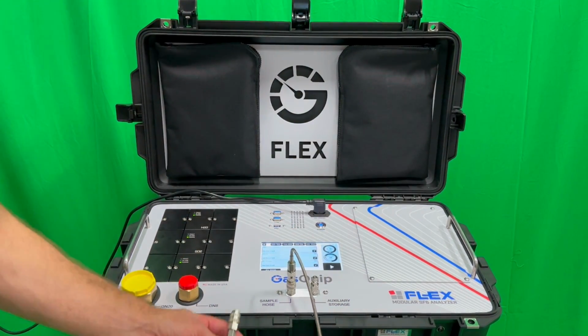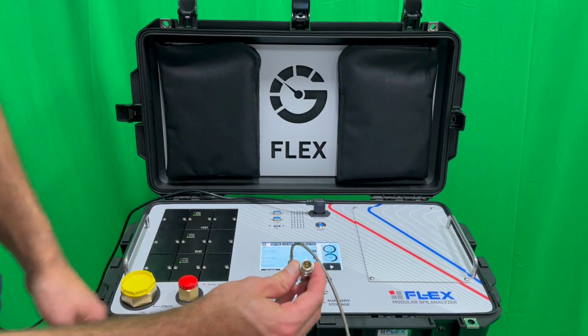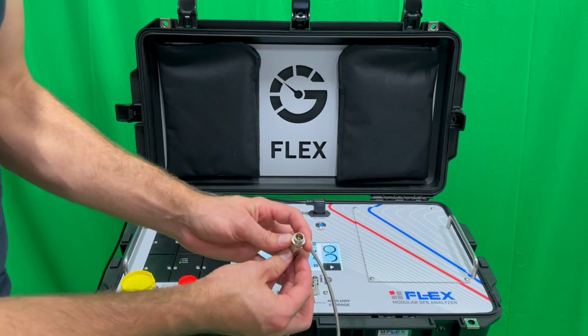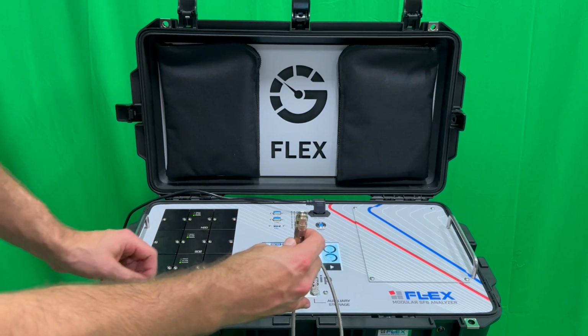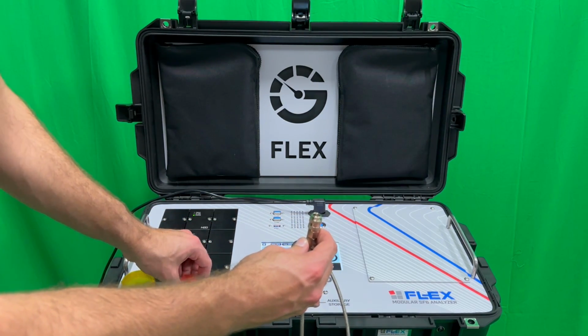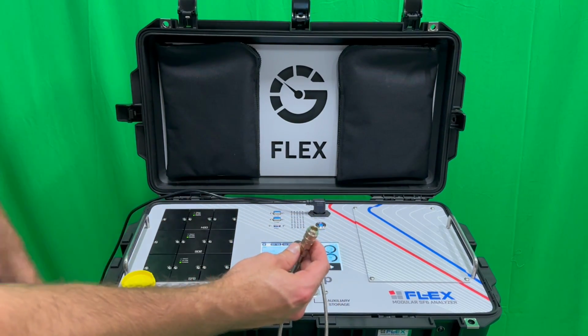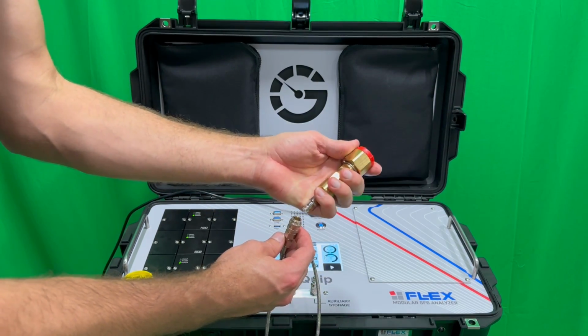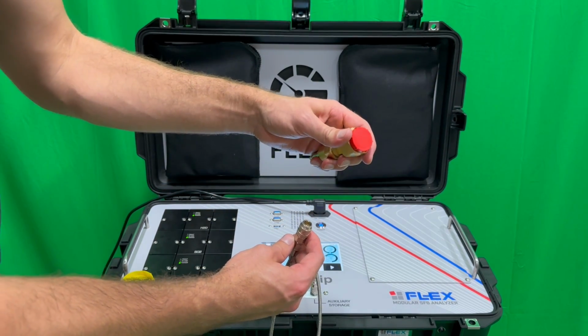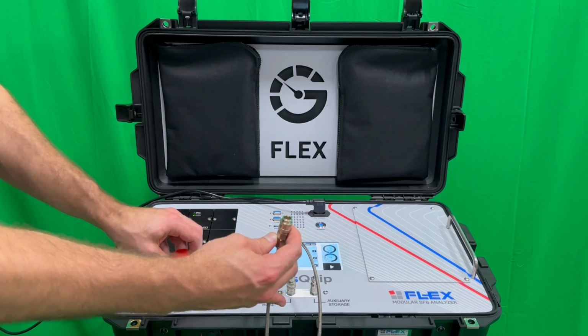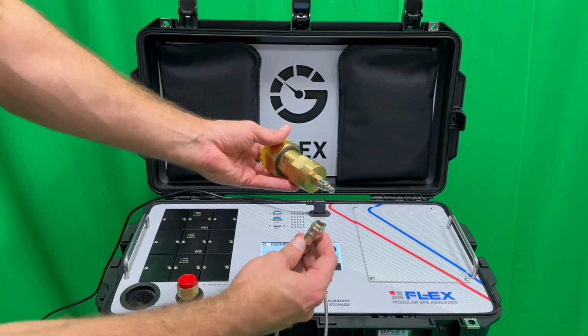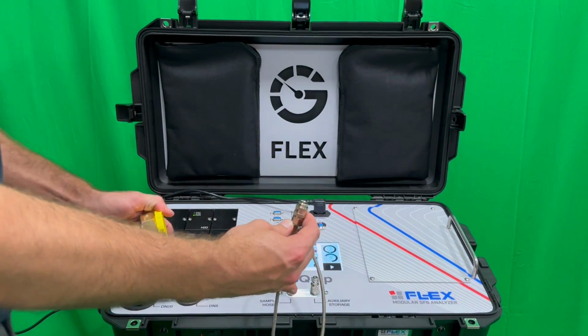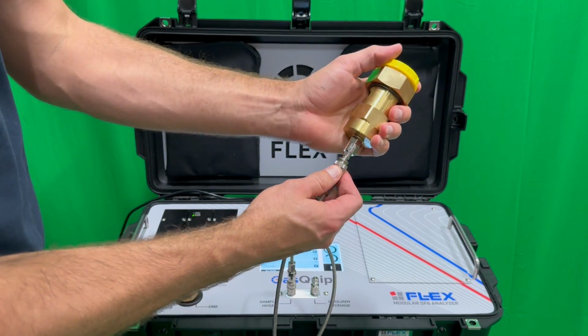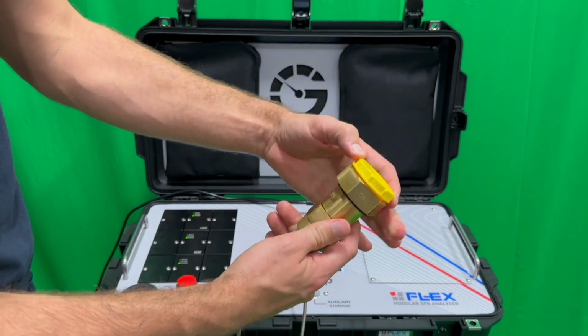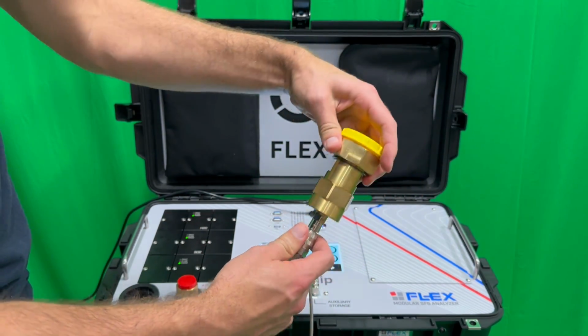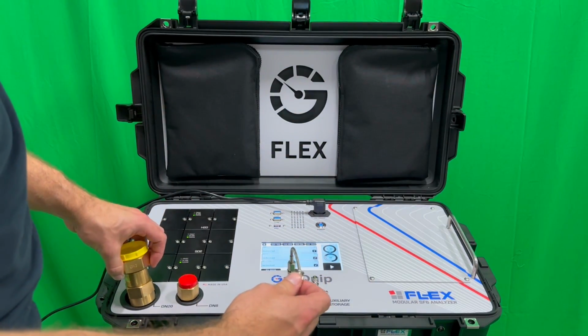The gas will come in from this side of the hose. Typically you'll hook this up to some switchgear, a circuit breaker that has a gas compartment filled with SF6, and you can adapt to it using some of the different adapter fittings we have here. This is a DN8 fitting, and we also have a larger DN20 size. You just hook this onto the end of the sample hose like that, unscrew your cap, and then hook it up to your gas compartment.